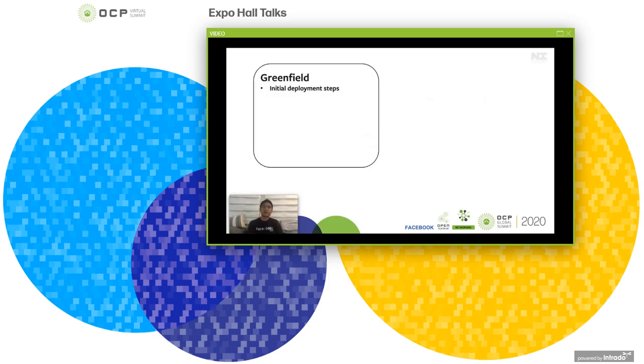So as part of the workflow to achieve this, we have an end-to-end workflow orchestration system that takes a look at all the different steps to do a deployment. And this is actually pretty complicated because not only do we want to have orchestration and workflow for the automated software pieces, but there are a lot of human-centered steps that we need to take into account as well. Actually physically racking and stacking and putting in servers or networking equipment, or hooking up thousands of different optics and circuits, which is especially complicated when you consider the other end of those circuits may be hundreds of meters away in a different building.